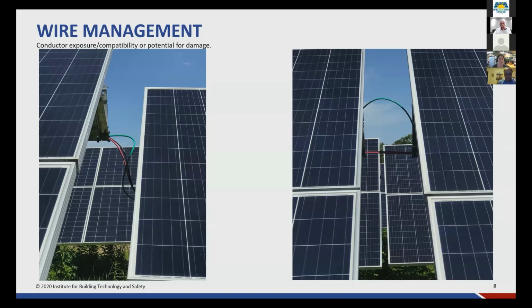If you look closer, you'd notice some method used for abrasion resistance. The second picture on the right shows the wire much more taut. If the arrays were to move independently, whether from erosion or some other expansion-contraction event, it's possible those conductors will fray over time. Not only possible, I'd contend it's likely that will happen over time. Good point. There's no scutcheon or wire chafing sleeve there to keep the conductors from sitting against bare metal.